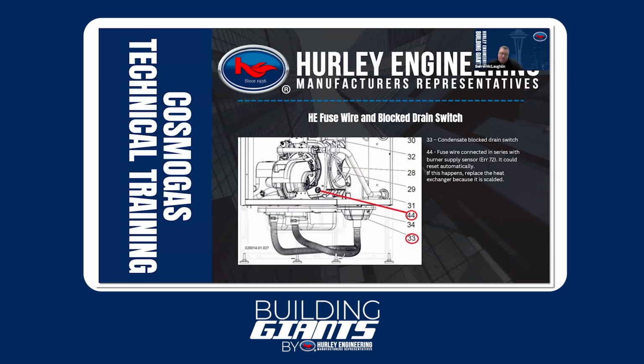There's one heat exchanger that has a base value of 250,000 BTUs output or input. And that heat exchanger has 15 wraps of the coil in the tube to be able to accommodate that much heat. Then there's a second heat exchanger that's a 199 output or input heat exchanger, and it only has 13 wraps of the coil. So they can take that 250 base model and stack it up to 4 times, and that gives us those options: the 250, the 500, the 750, and the 1 million. Or they can take the second heat exchanger, the 199, and stack it twice and go 199, 399 to account for those 2 models that fit certain codes and CSD requirements. So between those 2 separate and completely different heat exchangers, they can build 6 different models. Thanks for that clarification.